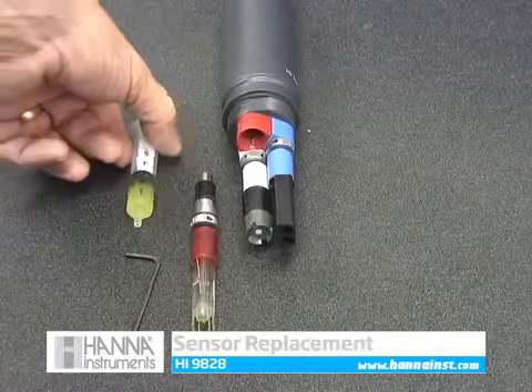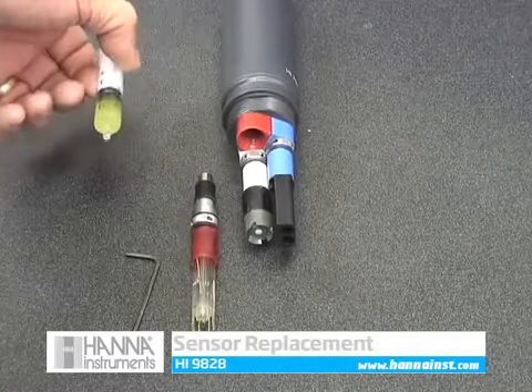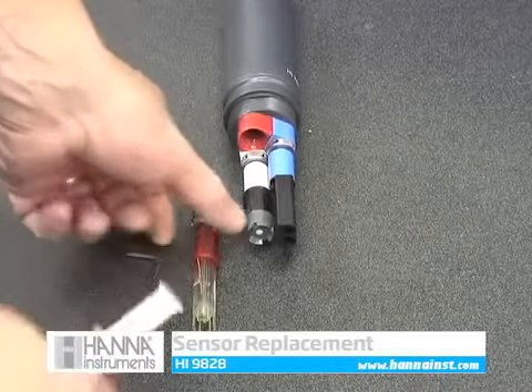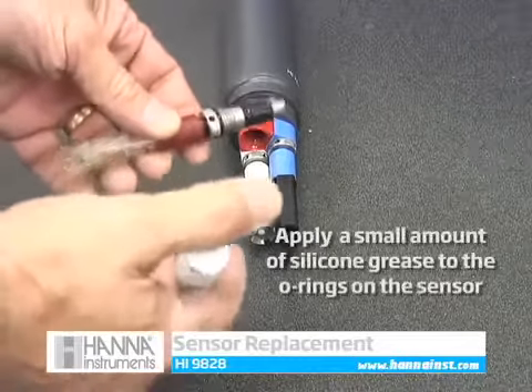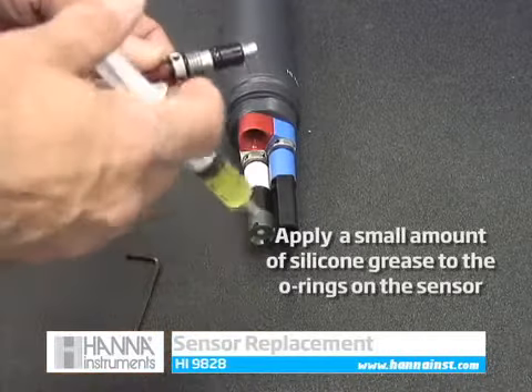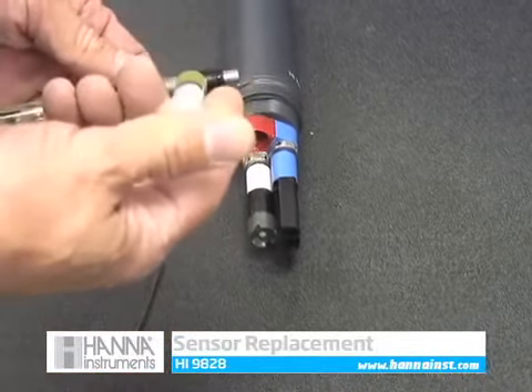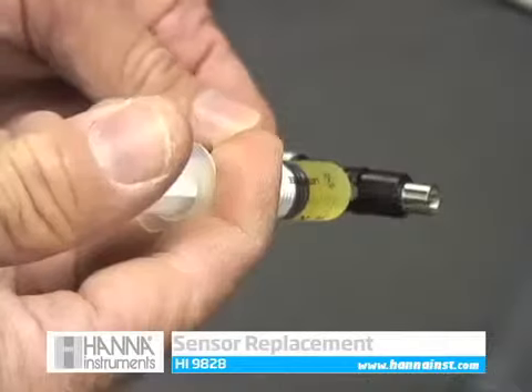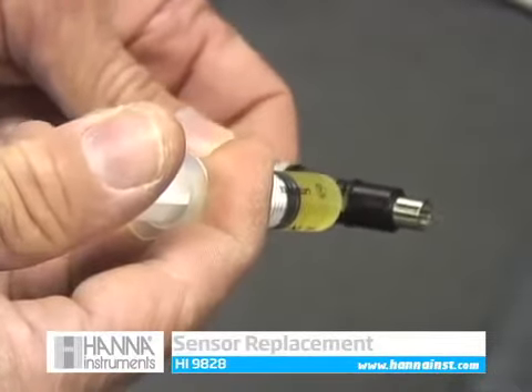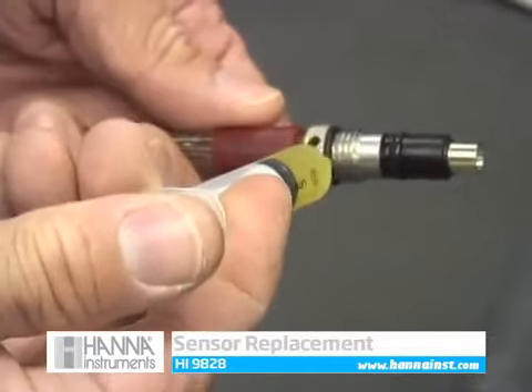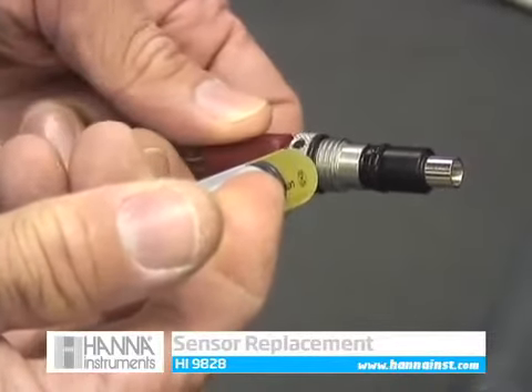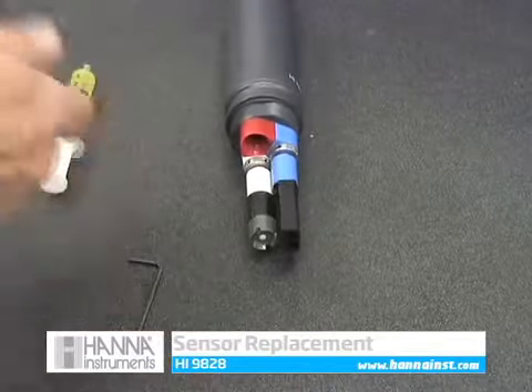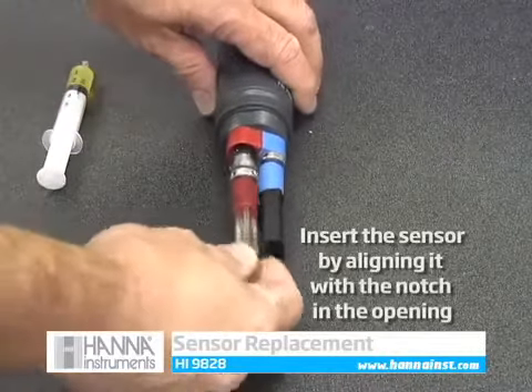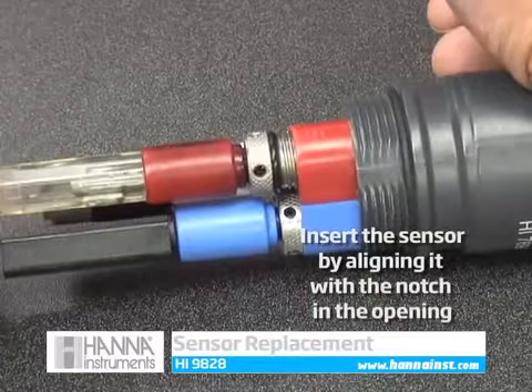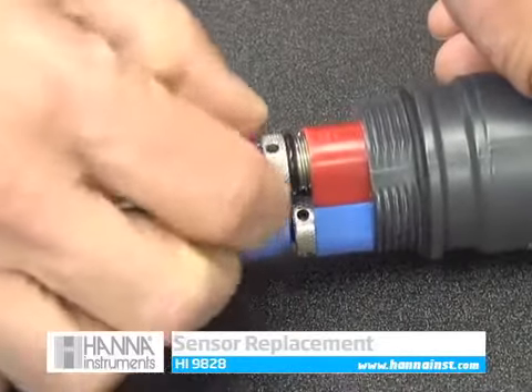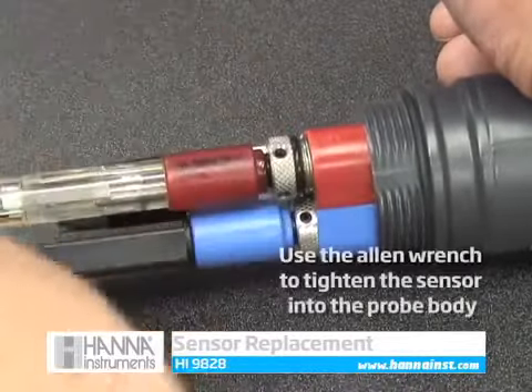Sensor replacement is easy, and we'll show you how. Here we have a plastic syringe filled with silicone grease. The included silicone grease needs to be applied to each of the O-rings before inserting it into the sonde. This will assure the integrity of the O-ring and seal. Next, insert the sensor into the sonde by aligning the notches and using the supplied Allen wrench to tighten the sensor's metal ring to create a secure seal.